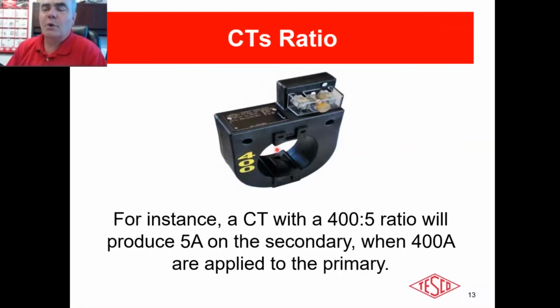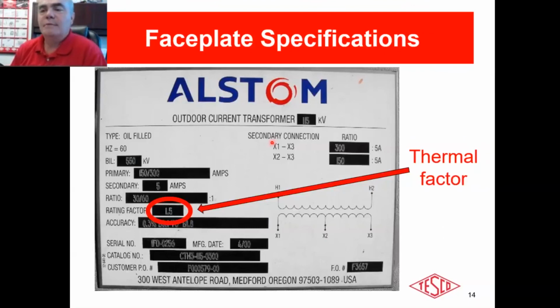All right, so on the higher ones, I definitely prefer the bar. In general, I prefer the bar, but that's just a personal choice. I could put a whole panel of 40-year utility veterans, and it could be pretty equal between donut and bar. It's just personal choice. What works best for your utility, use either one. They are both just as good for the applications, especially if you're not talking about 2,000, 4,000, 5,000 to 5s, whatever works easiest for you. Okay, so again, all this means is when 400 amps are applied on the primary, you get 5 amps out on the secondary. All right, the next one.